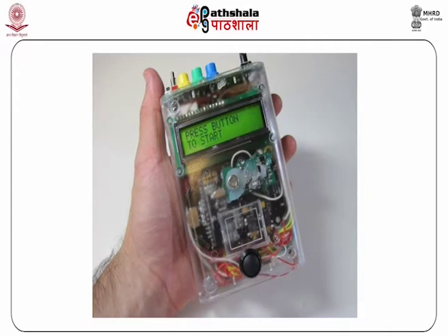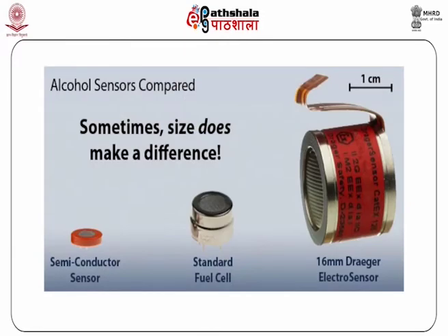Now we move on to calibration. Calibration is the process of checking and adjusting the internal settings of a breath analyzer by comparing and adjusting its test results to a known alcohol standard. Many breath analyzers use sensors made of tin oxide for measuring the BAC. These sensors are highly susceptible to interfering substances and are prone to contamination by substances other than breath alcohol. Such sensors thus require replacement or recalibration at regular intervals.